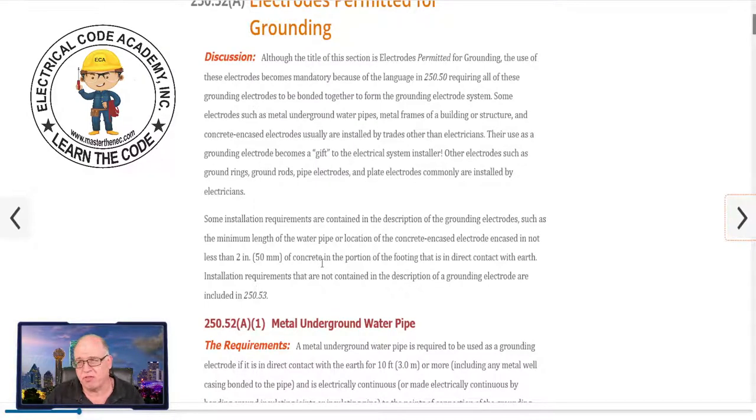Everywhere in the country is a little different. Some places don't require the vapor barrier; some may. Some areas may require the vapor barrier but allow the electrician to cut it in a small portion so that you do have at least that coverage area of the concrete — 20 feet — in contact with the earth. Check your local jurisdiction. If the concrete encasing that rebar is not in contact with the earth, you don't have a Ufer ground, and if you don't have a Ufer ground then it's not present. You've got to go some other direction — install 250.52 A4, A5, A6, or A7, and most people are going to do ground rods.